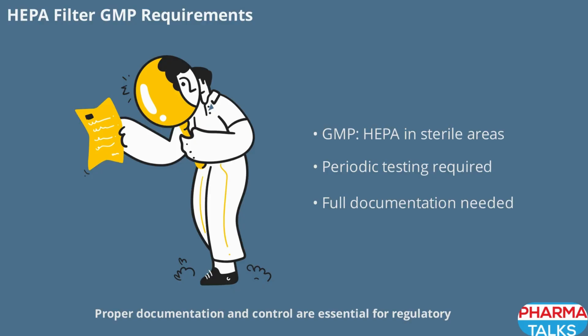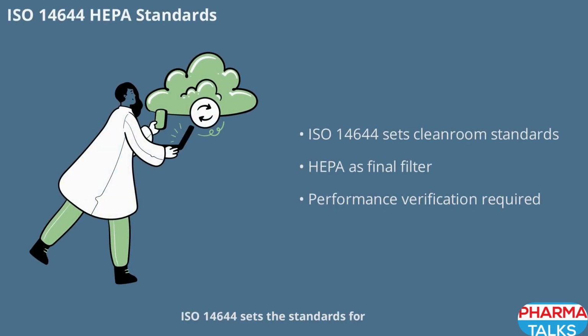Proper documentation and control are essential for regulatory compliance and for maintaining the integrity of sterile processes. ISO 14644 sets the standards for cleanroom classification and particle concentration limits. It specifies that HEPA filters should be used as the final stage of air filtration to maintain these limits. Performance verification is a key part of compliance, ensuring that the filters are functioning as intended and that the cleanroom maintains its required cleanliness level.